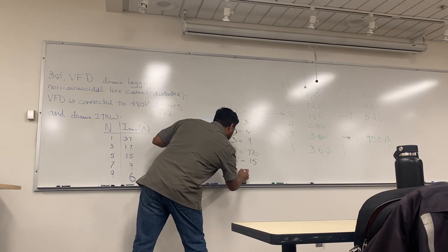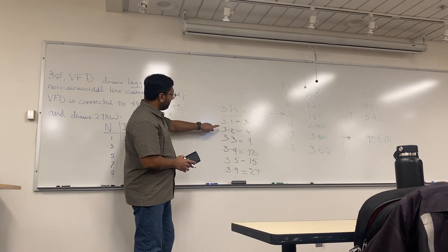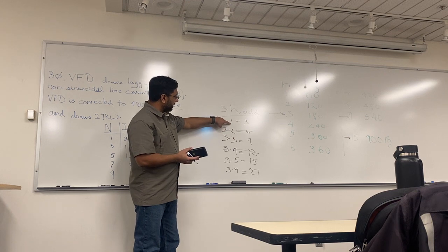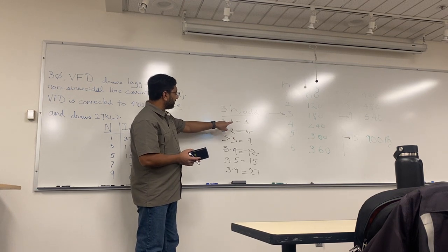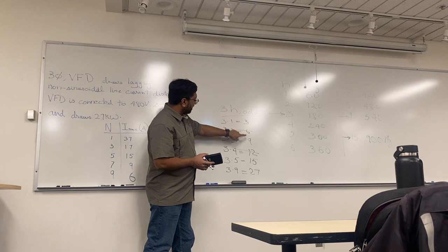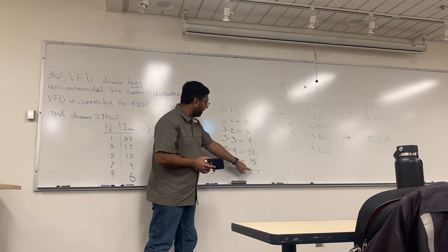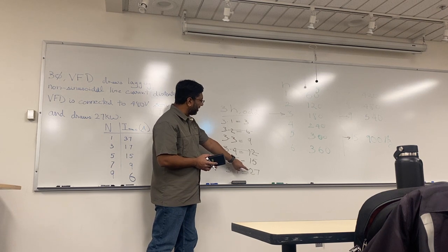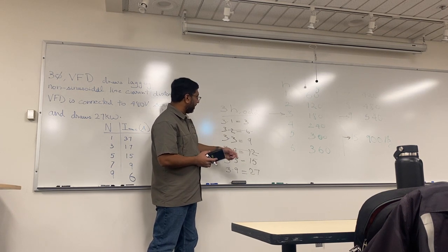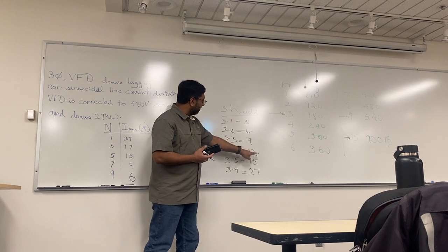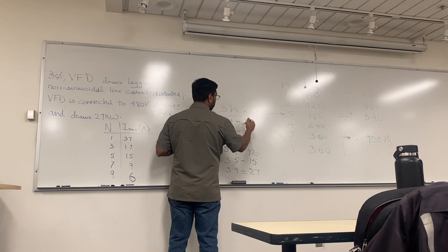Let's do 3 times 9, which is 27. So what this is telling me is my first harmonic, being the fundamental, is needed, but it's the third, the 9th, the 15th, the 27th harmonic that is going to be important, and it's going to cause some sort of an issue. And these are called the triplens. So 3h, and then pick the odd number. So this is my triplen.